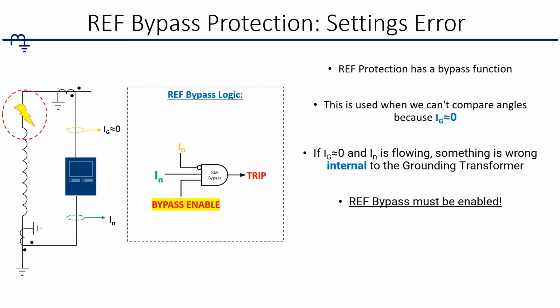And what that does is it says if I have IN flowing, so current's coming up from the neutral and it's contributing to its own fault and it's not leaving the transformer and going out into the network or some other network, that's unaccounted for ground current. So it's basically contributing to its own fault. So they wrote some logic in there that's saying basically not IG, meaning there's no ground current flowing, and IN. And here's the kicker, you have to turn it on. So there's a bypass enable.